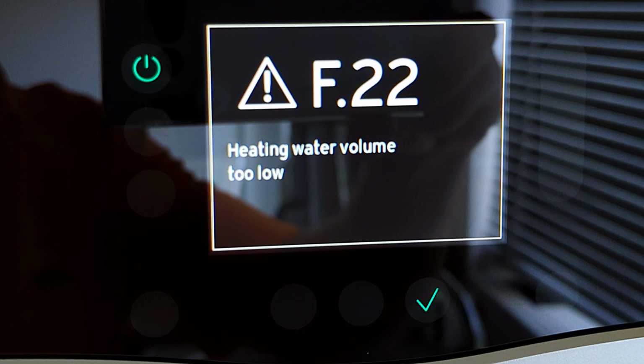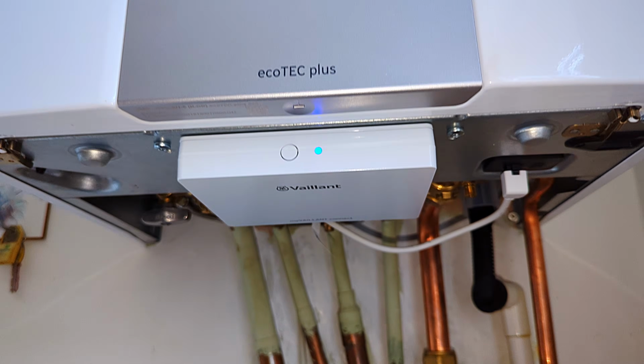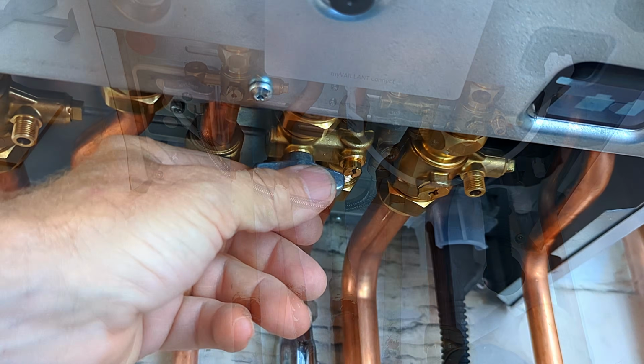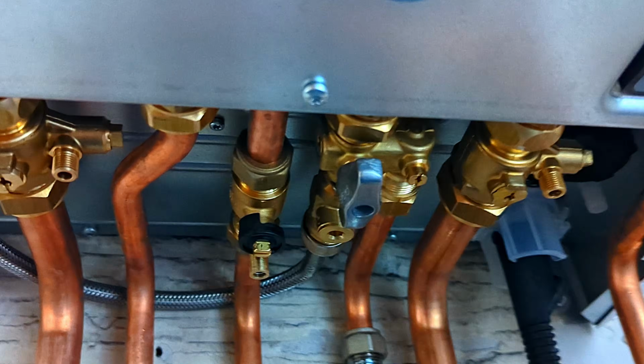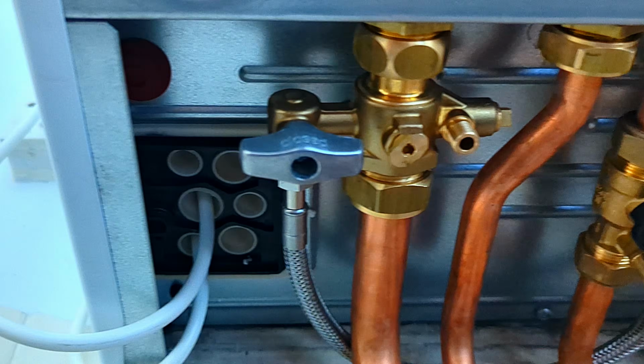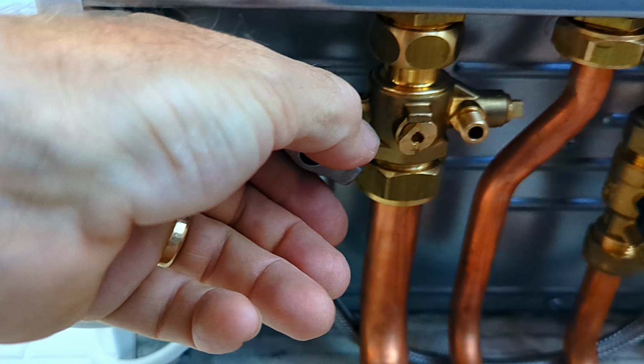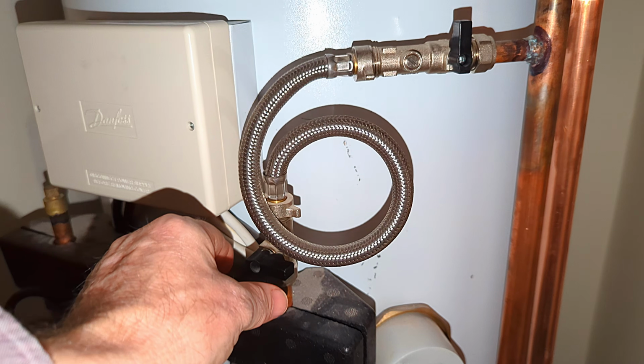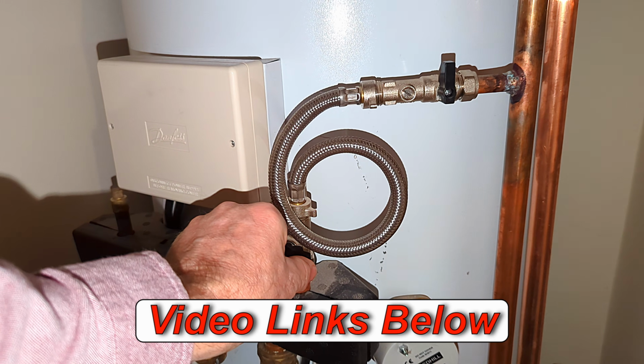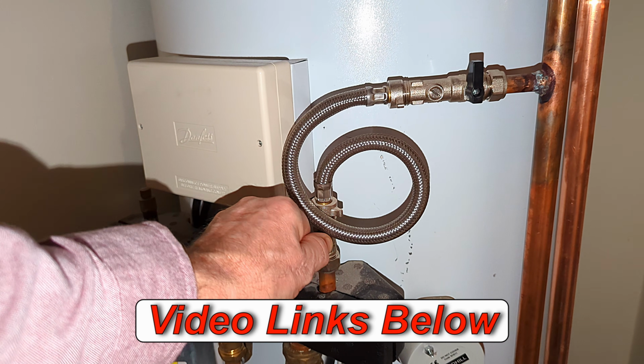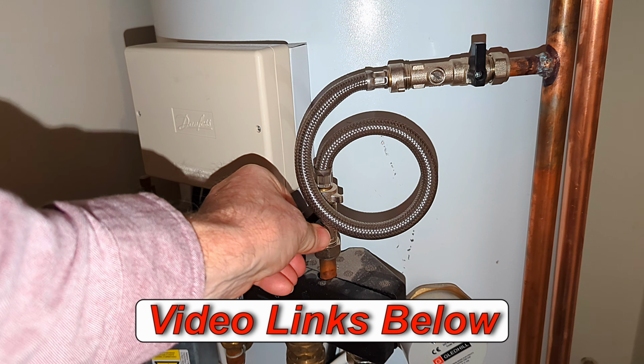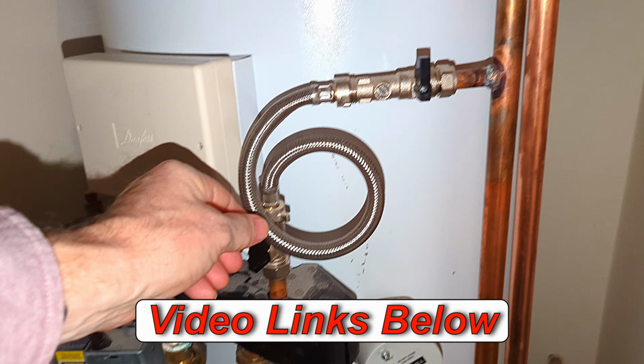Now if you get the F22 fault, that's pretty straightforward. You can fix that one yourself by just topping up your boiler. That's just a case of going underneath the boiler and topping it up with the filling loop. Or if you've not got a filling loop underneath the boiler, use the external filling loop and fill it up from there. Now I've made a completely separate video all about doing this, and I've left a link in the cards above or down in that description.